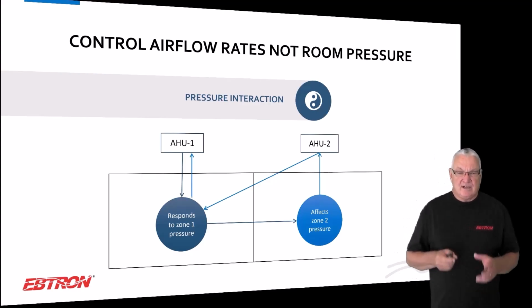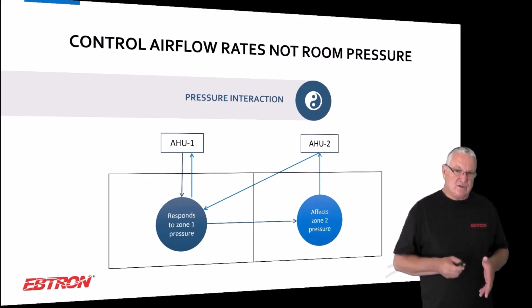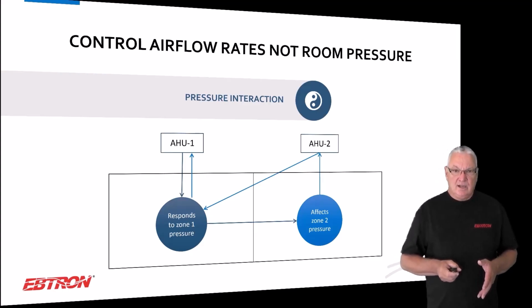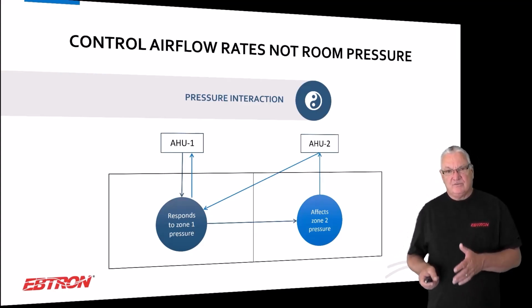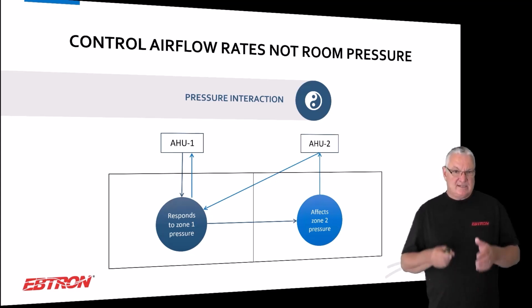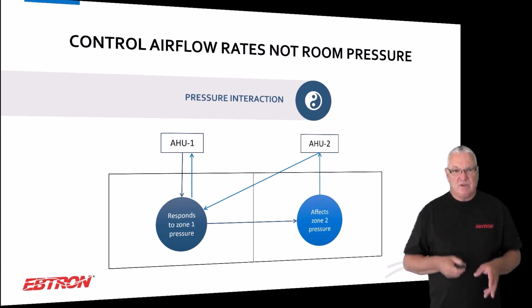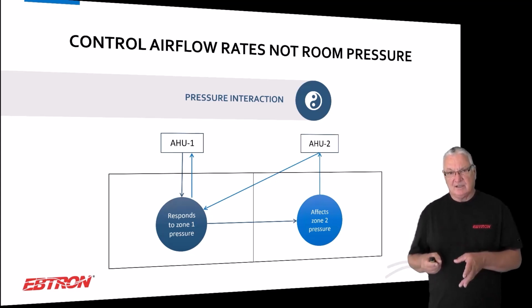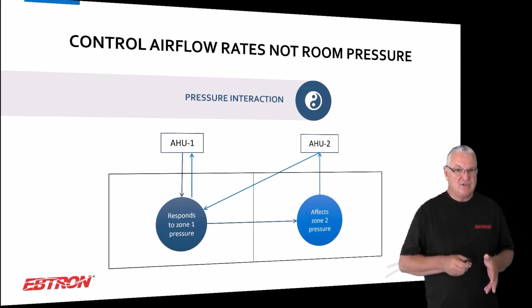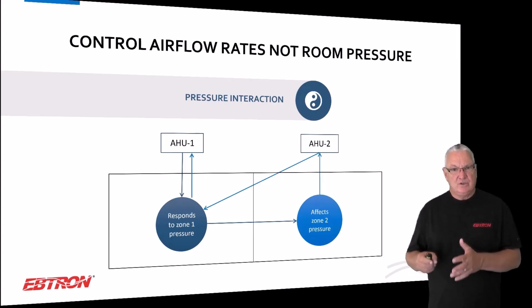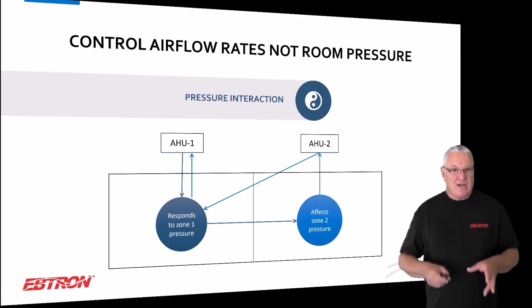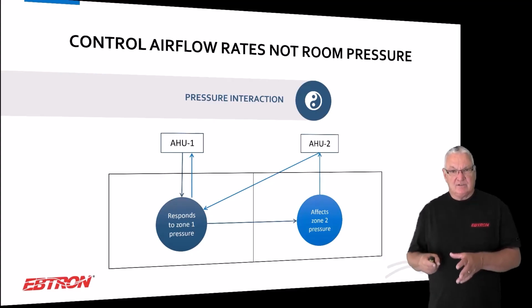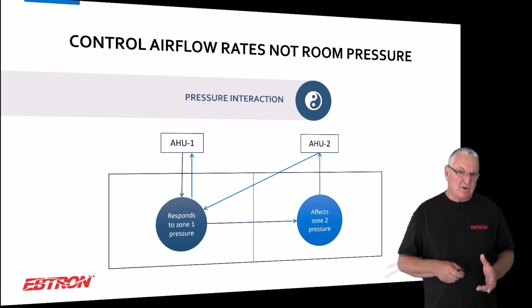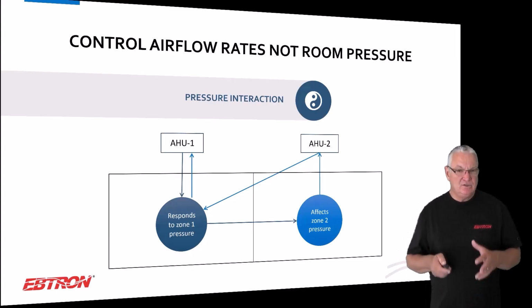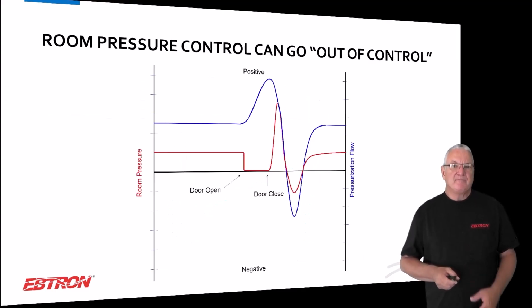Now, if I was doing airflow control, differential flow control on air handler one and differential airflow control on air handler two, yes, how I change the differentials between air handler one and air handler two will change the pressure relationship between those two zones, but it won't change the way air handler one or air handler two are controlling, so you can compartmentalize. It is a huge and fundamental difference.